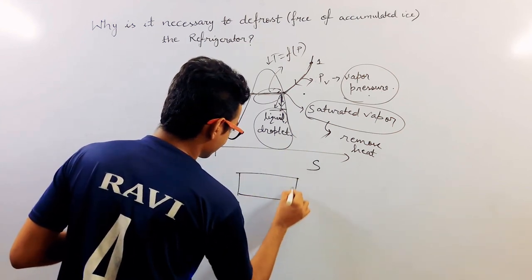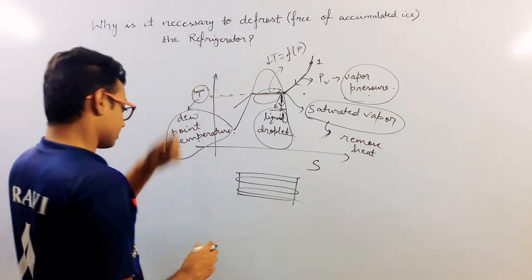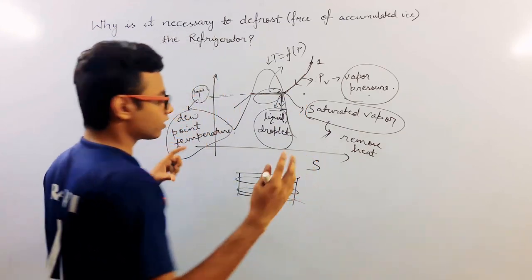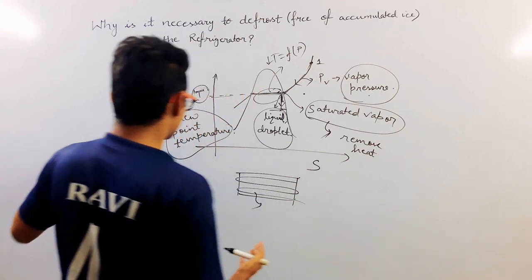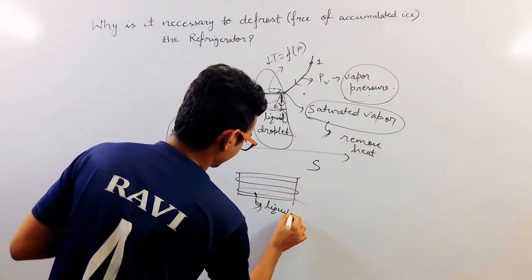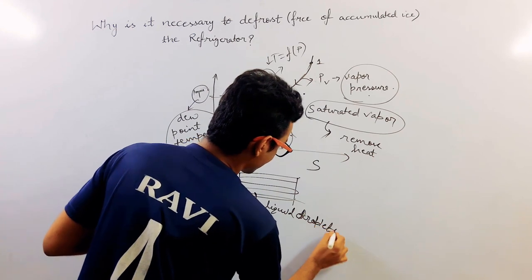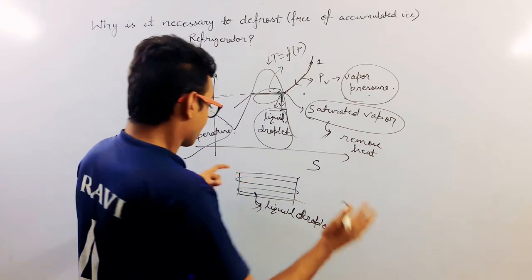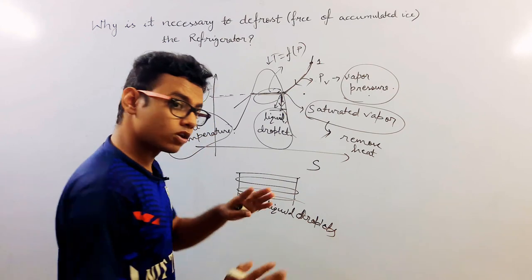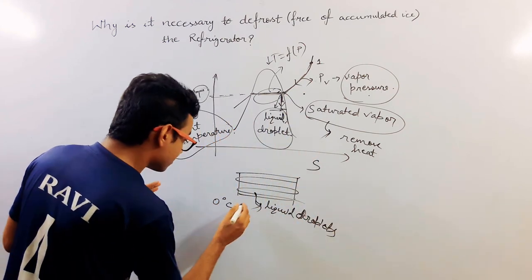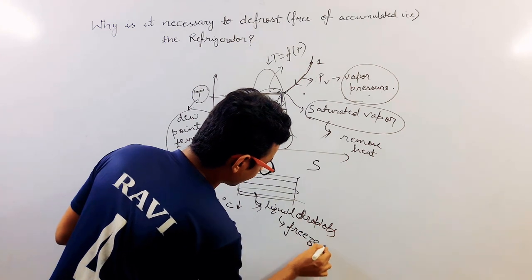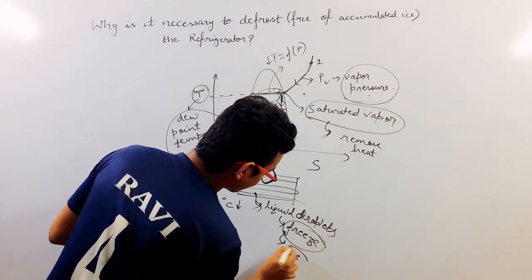Suppose this is the evaporator of refrigerator, and the temperature of this evaporator is below the dew point temperature. Because at dew point temperature, the condensation just begins, but no liquid droplet is formed. So just below the dew point temperature, or substantially below the dew point temperature, liquid droplets will form. And if the temperature is also below the freezing point of water, that is below zero degree Celsius, then this liquid droplet will freeze or it will convert into ice. And this is what is known as frost.